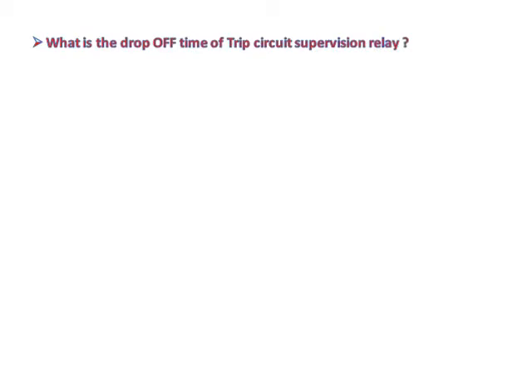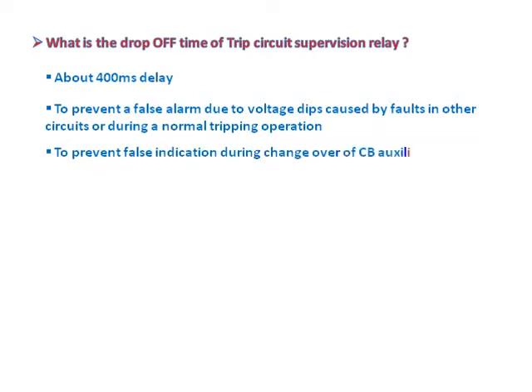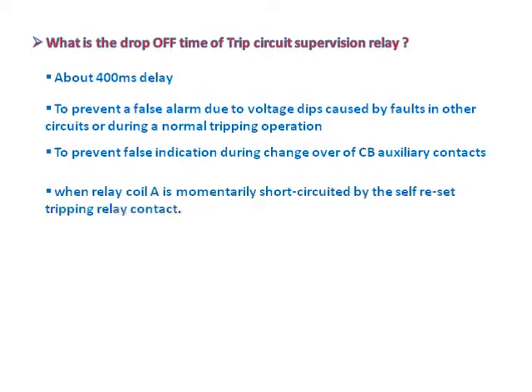What is the drop-off time of a trip circuit supervision relay? About 400 milliseconds delay — to prevent a false alarm due to voltage dips caused by faults in other circuits or during a normal tripping operation, to prevent false indication during changeover of CB auxiliary contacts, and when relay coil A is momentarily short-circuited by the self-reset tripping relay contact.